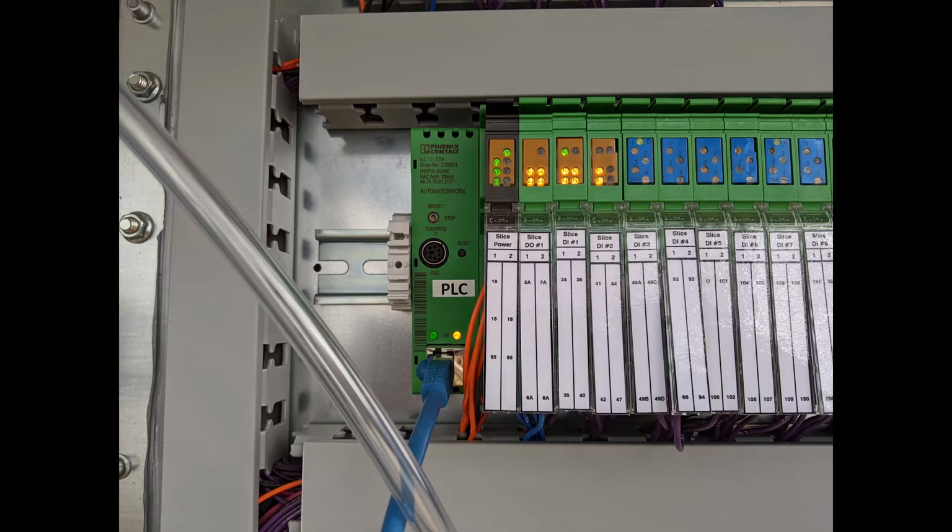First, we want to check that the HMI or the touchscreen and the PLC are both powered up. Now, obviously the touchscreen is, and it's because we saw the red screen. Then we want to go look at the PLC and make sure there's lights on the PLC. If not, we want to make sure the red E-stop button is pulled out. We want to make sure the green system control switch is into the computer mode. And if we still don't have it, we need to troubleshoot getting 24 volts to the PLC itself.